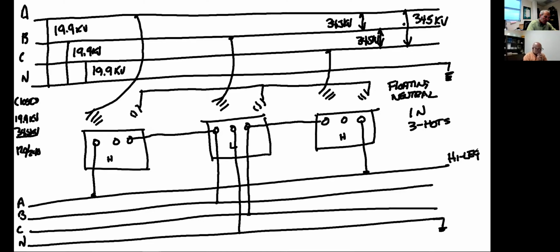Okay. This is where some people get tripped up a little bit. Secondary voltages. A to N, B to N, C to N. A is my high leg. Okay, that beginning voltage is 120. What do I need to do to that because it's my high leg? Multiply it by 1.732. Yeah, excellent, excellent. Which is 208. All right, the rest of them are phase to ground. 120, 120.